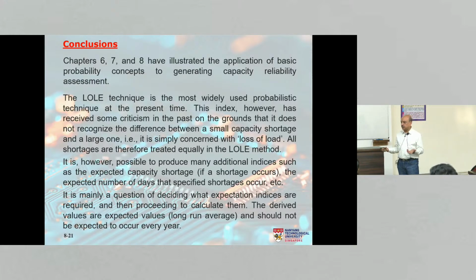The general notation you should know. This is the energy I'm not able to supply. Very simple. Whereas the loss of load expectation is the number of hours per year that my load is not supplied, right? Or days per year that I'm not able to supply the load. So that's a fundamental difference between the two. The LOLE technique is still the most widely used probabilistic technique because of its simplicity, perhaps, because there is a reference there, 0.1 days per year.